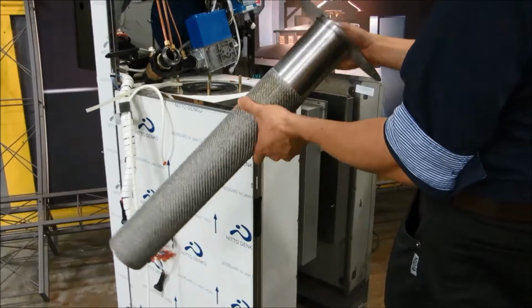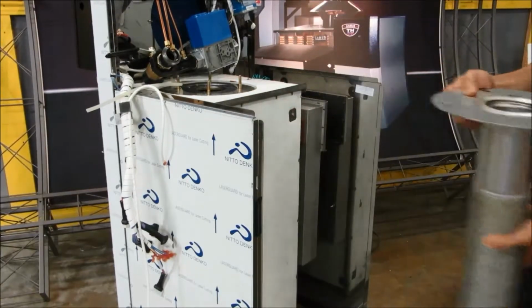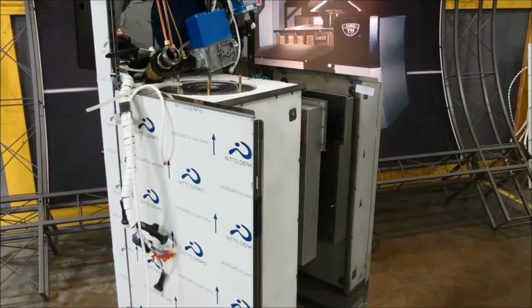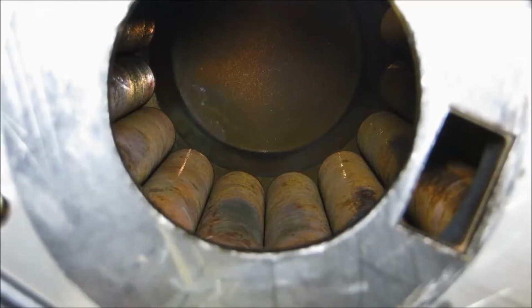Check the tightness of the fiber mesh. If the mesh is loose, this will lead to ignition failures, and it is not advised to reinstall the burner in this state.